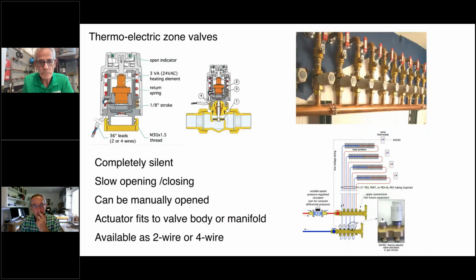Yeah, and it's probably not the best valve if you're going to put a valve right into a baseboard enclosure or into the enclosure on a unit heater, where it's going to be surrounded by hot air. It's definitely going to take longer to close in a situation like that.